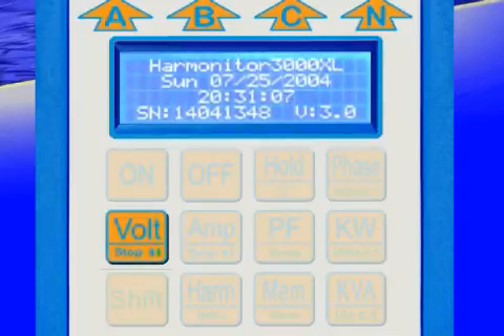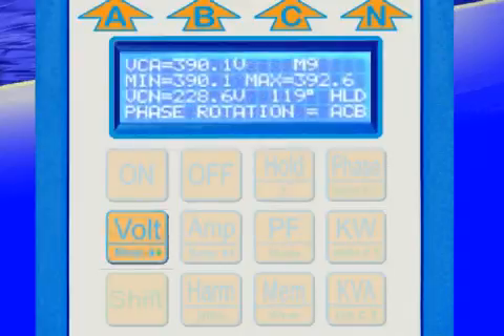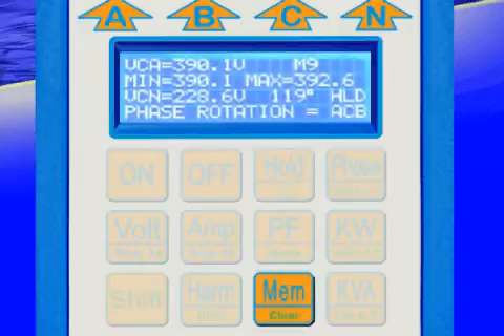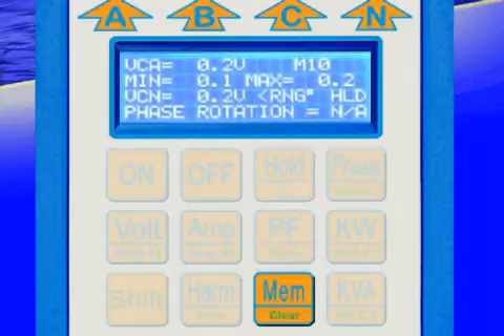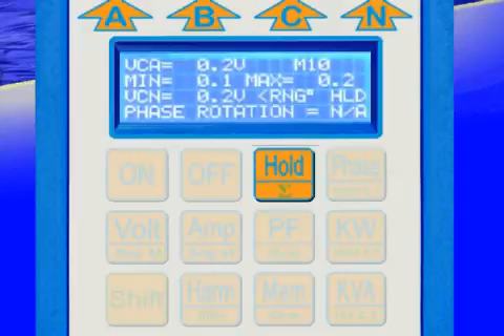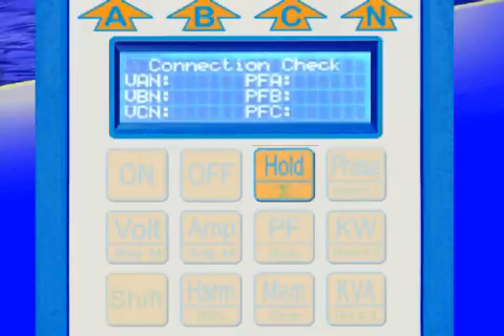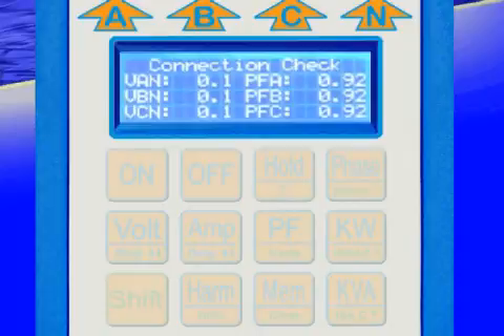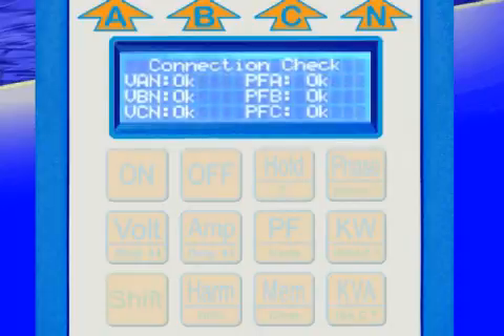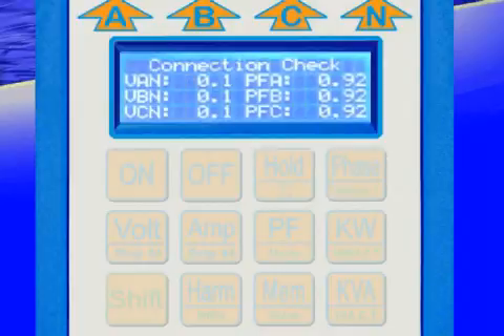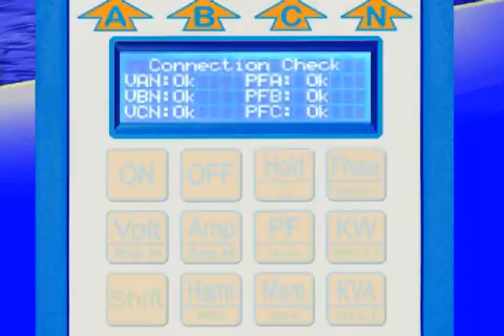Press Volt to get past the startup screen. Next, you will need to select the memory location you wish to save a snapshot in by pressing and holding the Mem key until the memory location you want to use is selected. When you are ready, release hold by pressing the Hold button. You will now see the connection check screen. This screen will indicate if you have properly connected the CTs and voltage leads. If there is a problem with your connections, correct them before moving on.